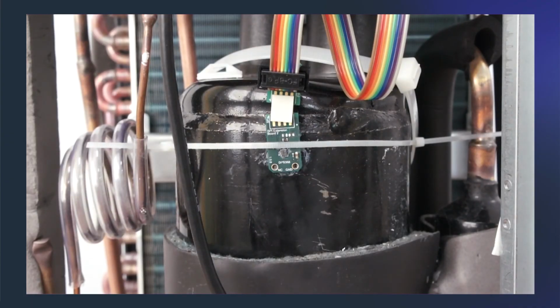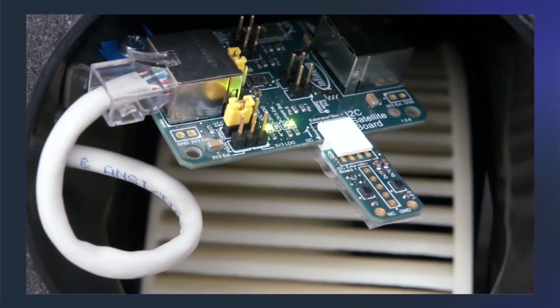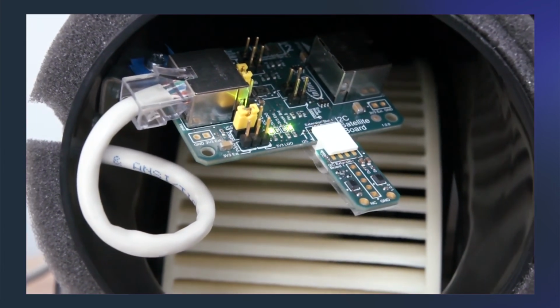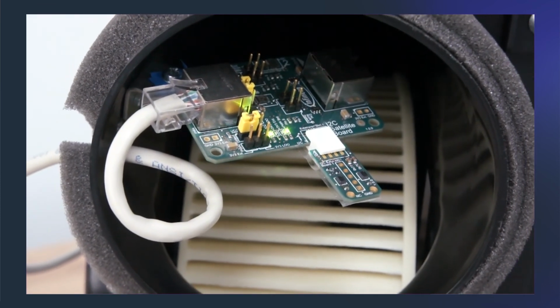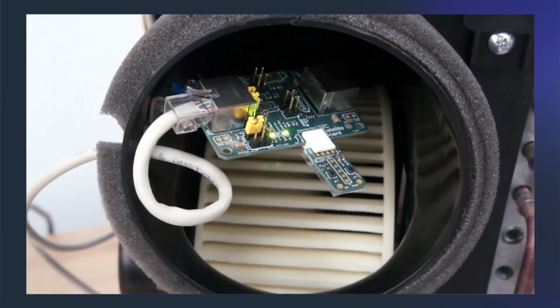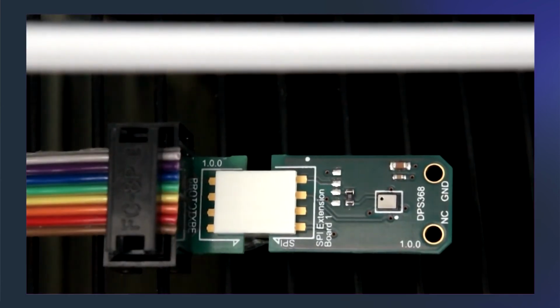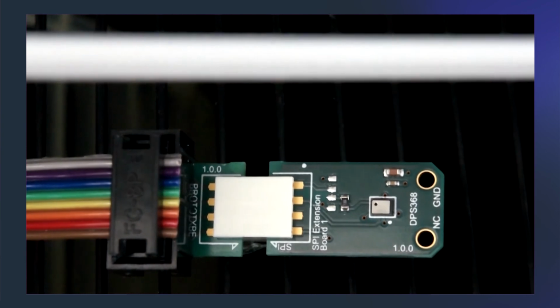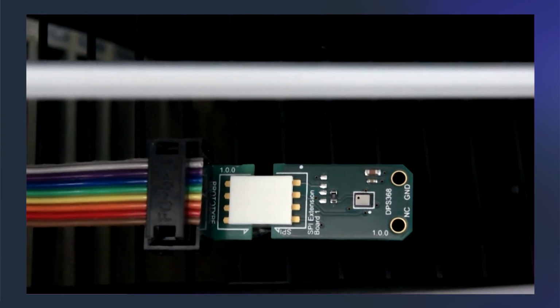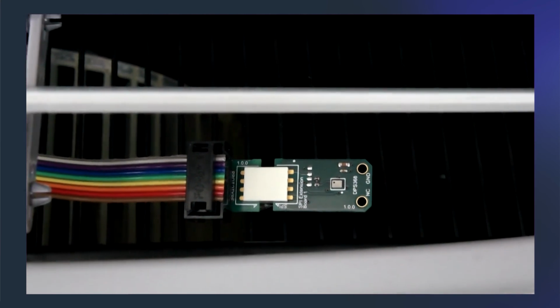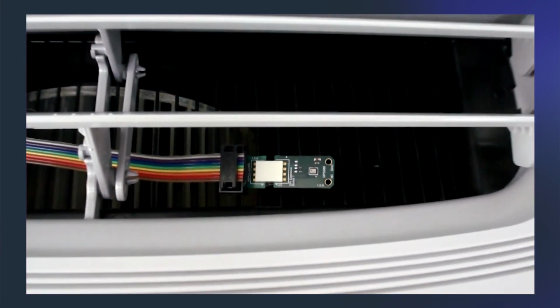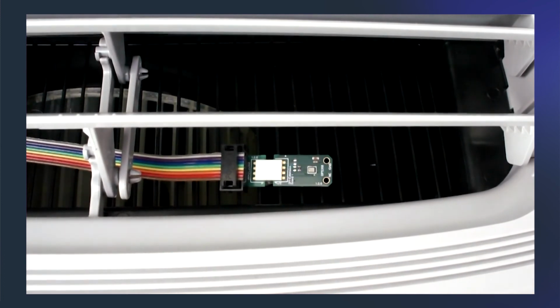So here we can see one of the temperature sensors. It is used to measure the compressor body temperature, which should be in an acceptable range. If not, then the compressor should be considered near to failure. Another two sensors are used to measure the air temperature coming out of the fans, both cold and hot. In case the cooling system works fine, it shows a value around 0 for the cold outlet and more than 40 degrees Celsius for the hot outlet. This sensor has an outstanding characteristic in measuring pressure. As the fans blow, it increases the pressure on the sensor relative to the atmospheric one. So it could be compared and checked whether the fan air is blowing or not.